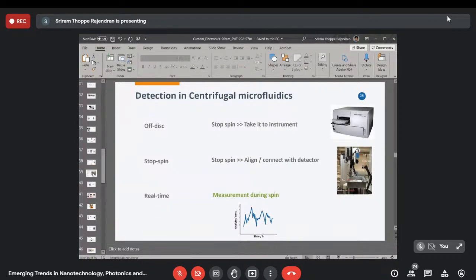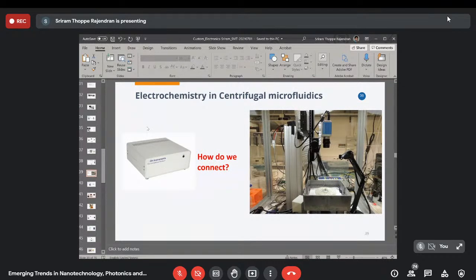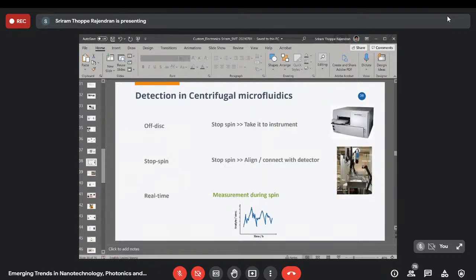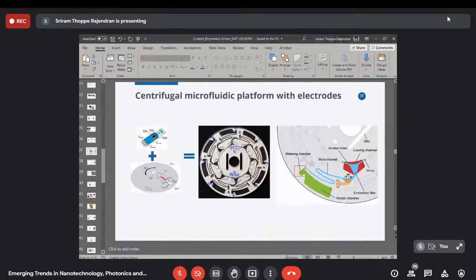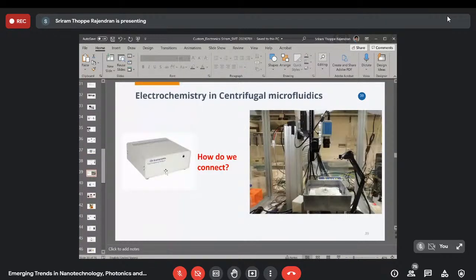More specifically, electrochemistry in centrifugal microfluidics is more complicated because this instrument has to be physically connected to the electrodes, because we are measuring current. These are contact points on the electrode. So we need to physically connect the electrodes to our instrument, which is here, and this disk is spinning. So how do you imagine doing this? How can we solve this problem?